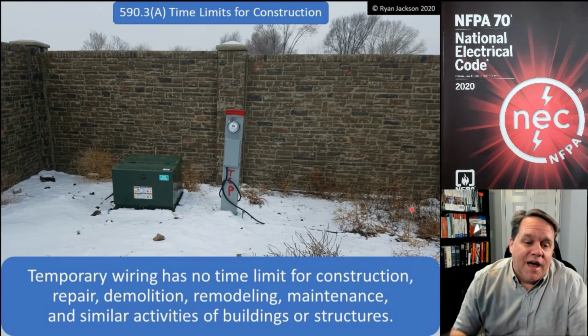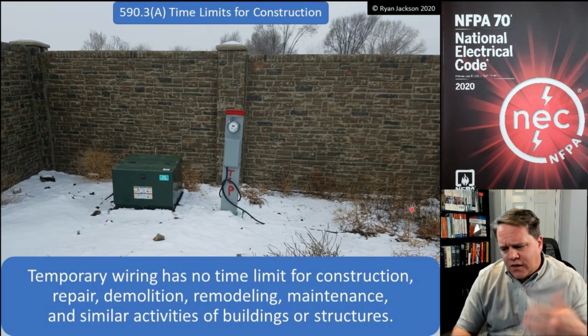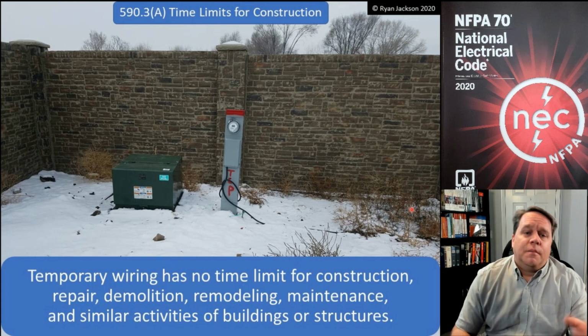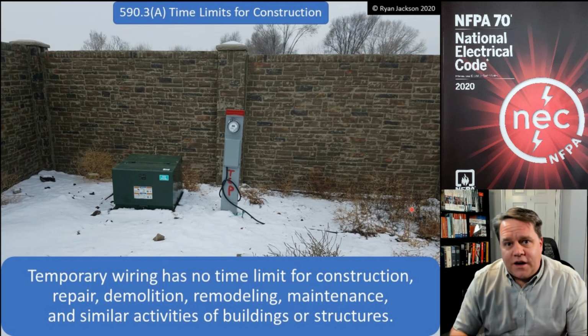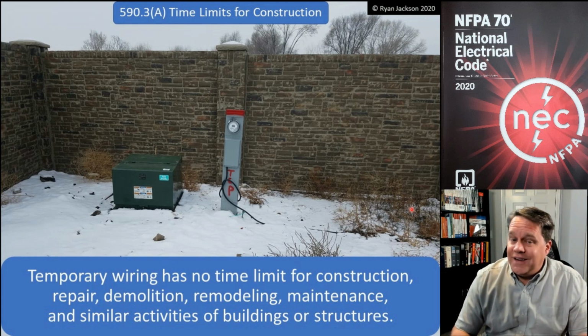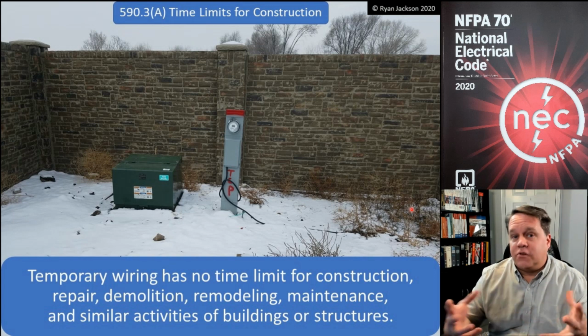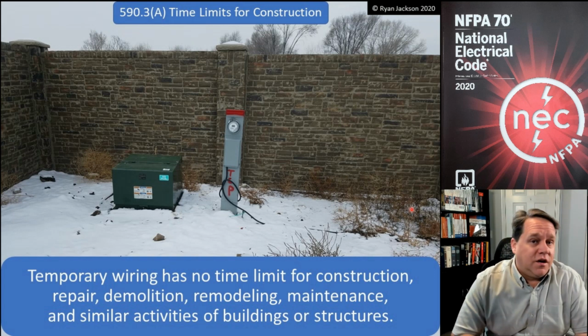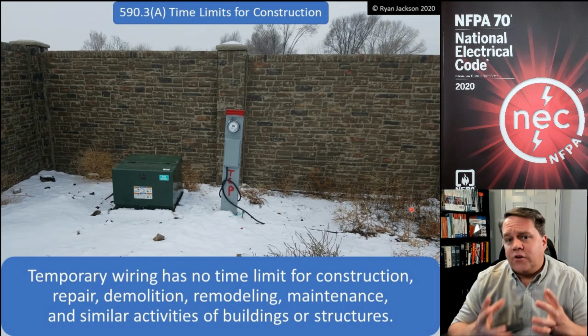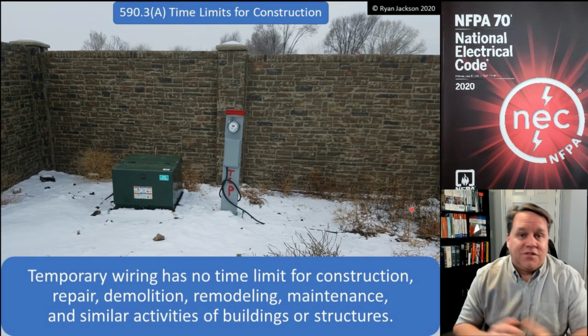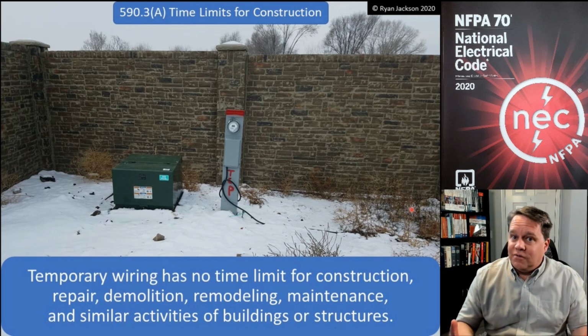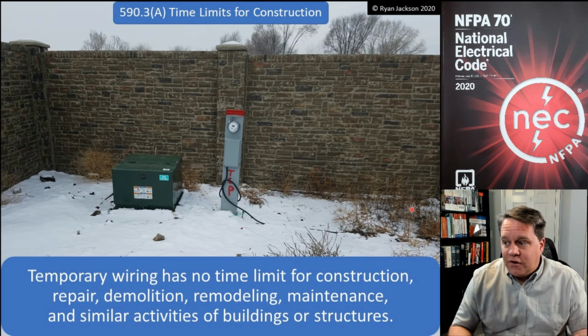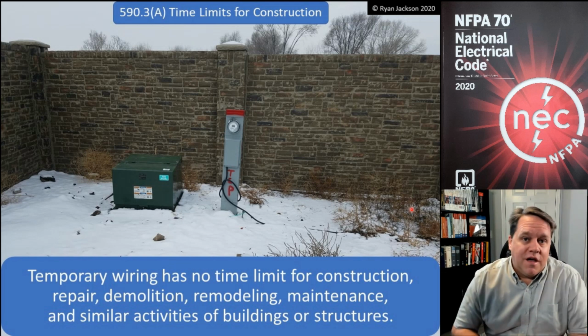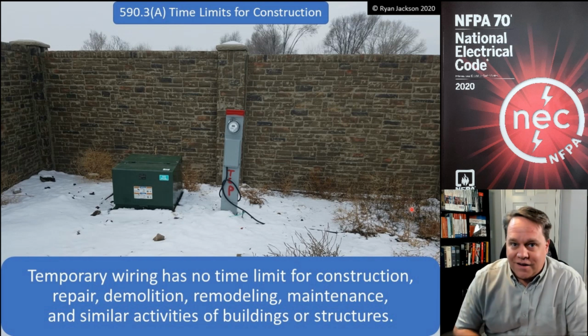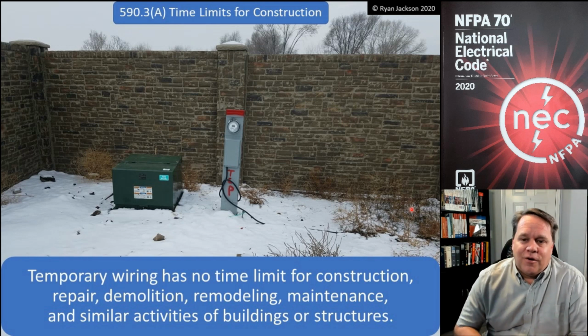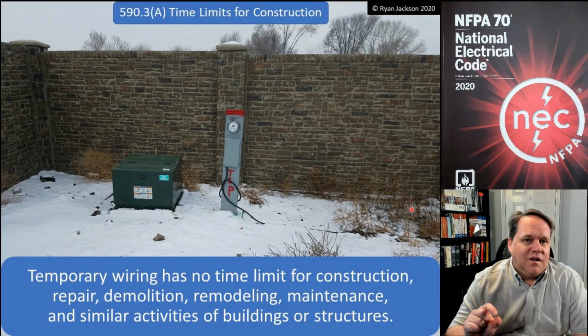Time limits, 590.3(A). It's kind of funny. A lot of people, when you talk about temporary wiring, the number 90 comes up as, oh, you've got a 90-day limitation. No, you have a 90-day limitation for holiday lighting, like Christmas lights that you might have out in your front yard. That's where a 90-day limitation comes in. When it comes to actual construction activity, there is no time limit. I mean, think about it. How many buildings really get built in 90 days? Maybe small residential and small commercial, but if you're doing anything even somewhat complex, 90 days just isn't going to do it. So there is no time limit as far as construction activities.